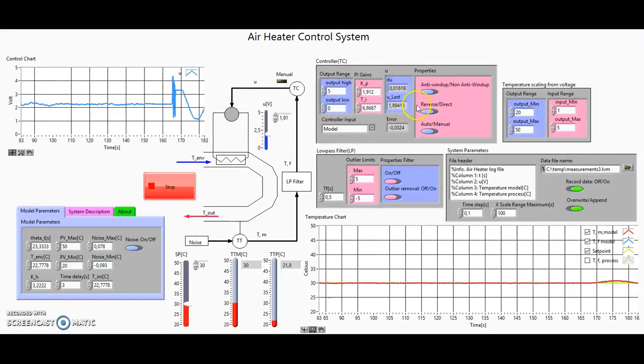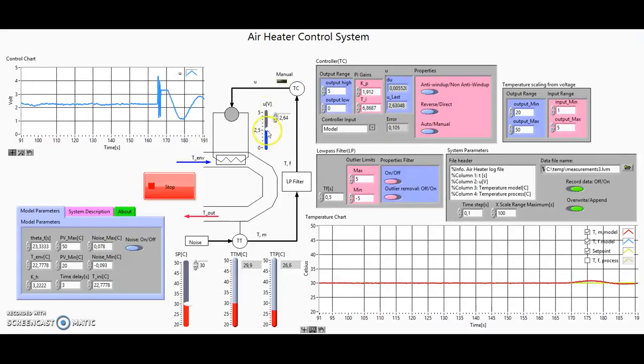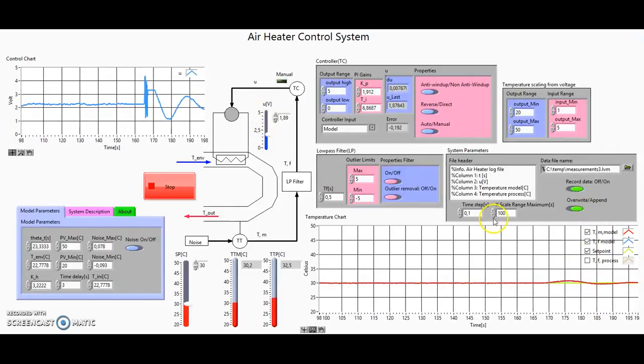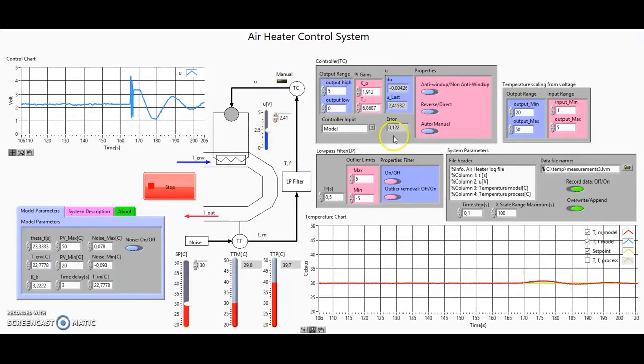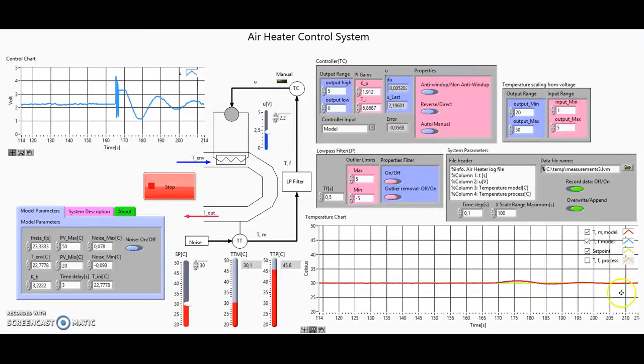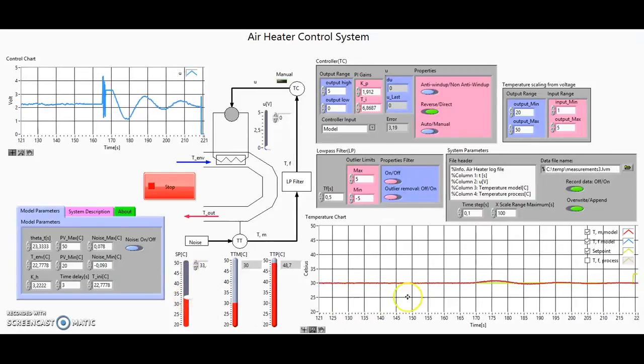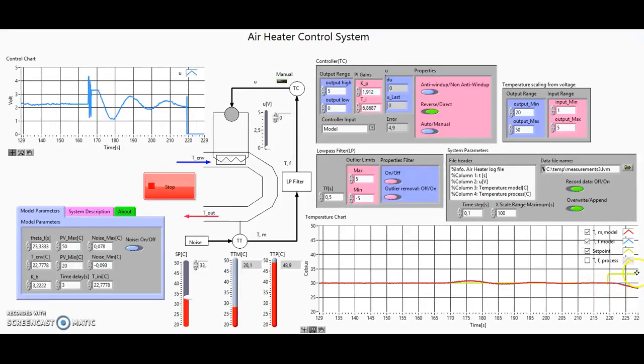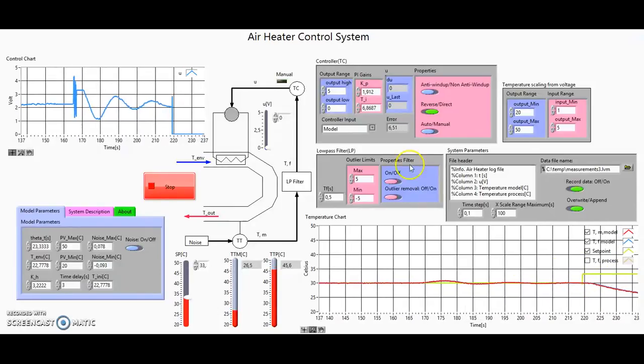You can also change the action of the controller between reverse and direct. This system is a reverse-acting system: if you increase the control signal, temperature will increase. For example, in a direct-acting system, instead of controlling a heating element you could control a fan — the more control signal, the faster the fan and the cooler the system. We now set the set point further and you can see it decreases instead of trying to control against the set point. If this had been a direct-acting system it would now be trying to reach the set point instead of going away from it.